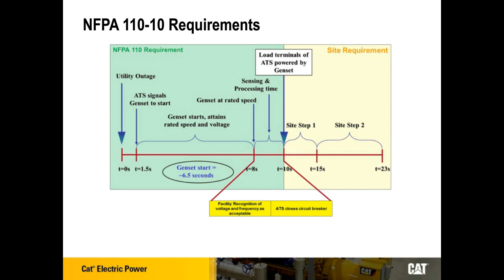One other thing on this timeline that I wanted to point out, because it'll be important later on: if you see on the yellow area of the timeline, we have two load steps. There could be any number of load steps, and this is particularly important for gas standby generator sets. It's helpful if we can segregate the life safety loads from other loads, assuming there's a significant portion of other loads on the generator set, which is pretty typically the case. We'll talk a little bit more about that later on.